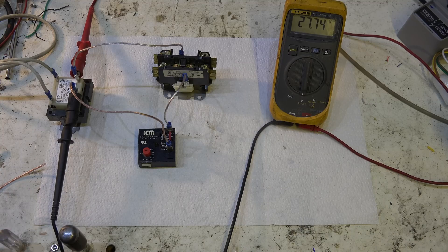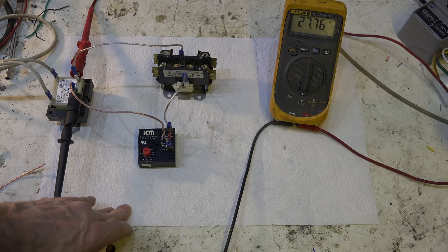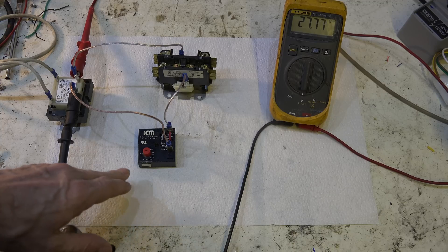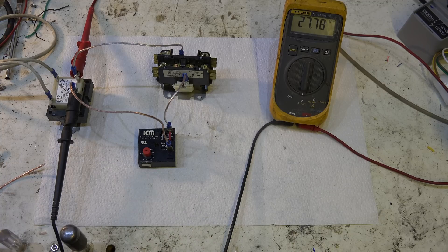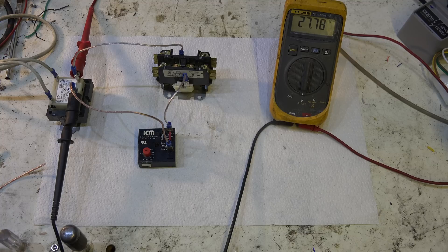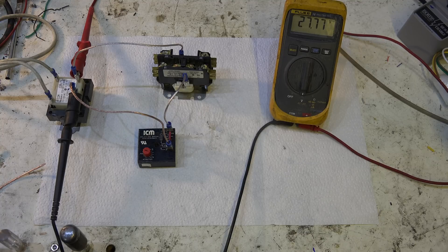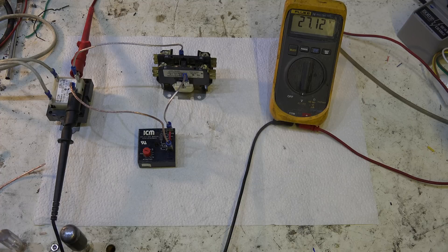And I'm not going to make you wait the whole time for it, but it's going to, in about a minute, it's going to turn on that contactor. You heard the contactor close, so it did its time delay.